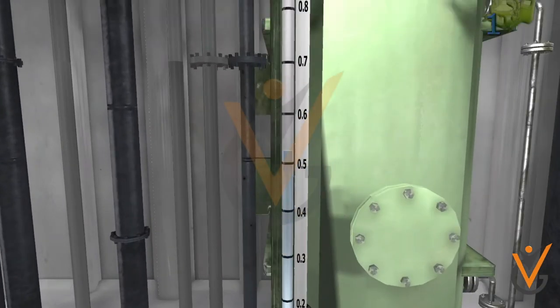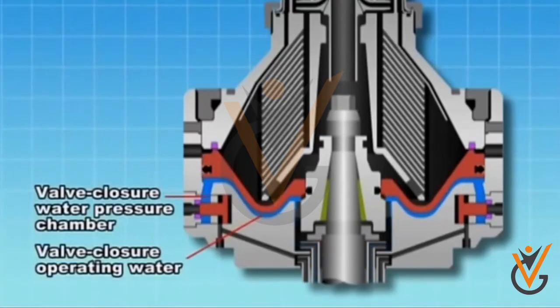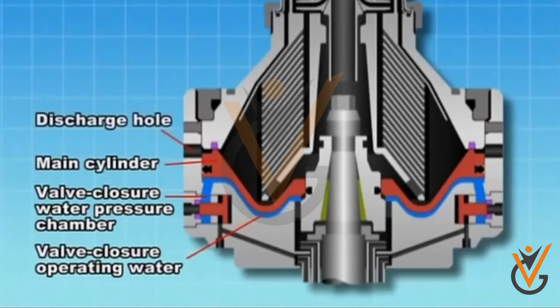Bowl Closing Water: This water comes from the header tank, which is located above the height of the purifier and supplies the water to the water paring disc to close the sliding bowl so that desludging ports can be covered.